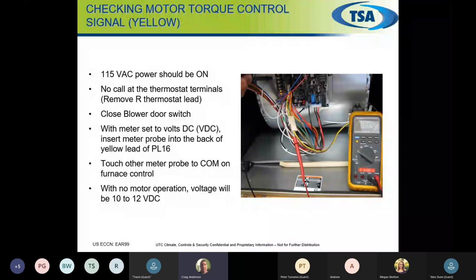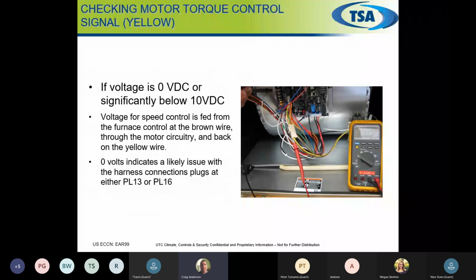So if we're not getting voltage back from that motor, if we're getting 0 with nothing running, or we're getting under 10, then we need to start looking at wiring harnesses or a motor control issue. We know we have our 15 volts DC going to the motor. That is constant. Everything is hunky-dory.